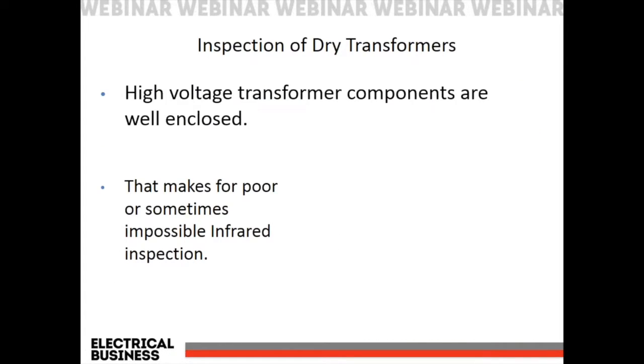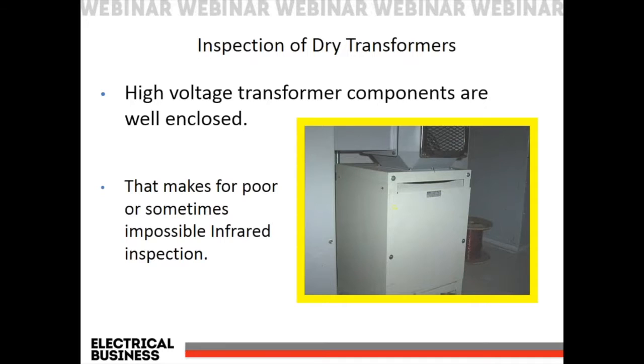All right. Inspection of dry transformers, again, we talked about earlier, can be hard to do. Components are well enclosed, and that can sometimes make infrared inspection impossible, unfortunately. But we can scan that air vent, and we can determine if something's going on before, obviously, a problem can occur. Now, there is a story about a transformer, not this particular one, where this was happening years ago from one of our customers, where he got the call to say, we've got a problem with our transformer. Can you analyze the sounds for us? So our electrical engineer in New York diagnosed this sound, and it literally was arcing. And he told the guy, listen, it's arcing. And unfortunately, it was a Friday afternoon in the summertime, and they left it until Monday, and hopefully nothing was going to happen.